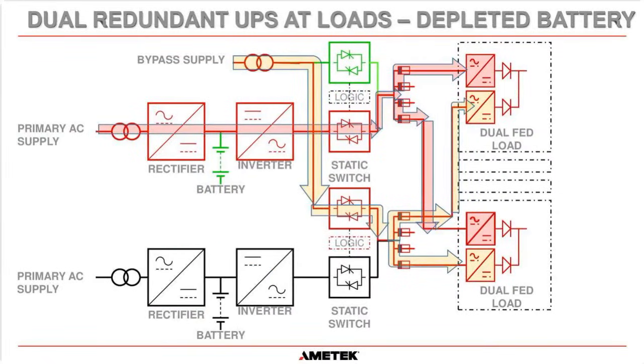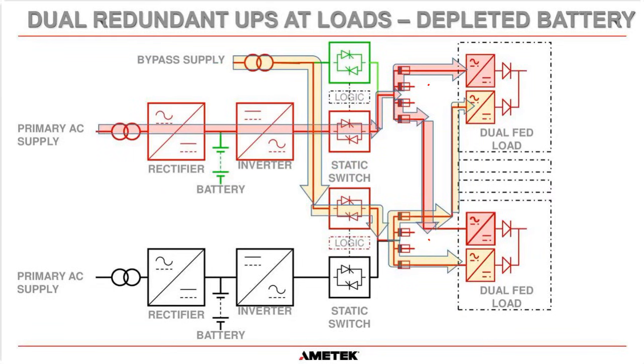So I'll go back to that one again. This is a very robust system, but obviously you need to ensure that all the loads, because this is usually an AC panel, and it will be labeled UPS-A AC panel, and this one here is UPS-B AC panel. The only thing that happens when you have a system connected like this is some people will attach a load to UPS-A, and they won't replicate that load on UPS-B. That's when you start to have issues, because if you took this whole system down for maintenance and only relied on this power supply, then if you connected a load to this one, but not to this one down here, that load will de-energize. So you do have to be careful to replicate all loads when you connect a system like this.